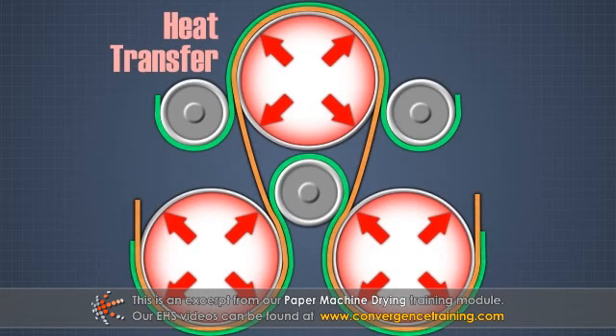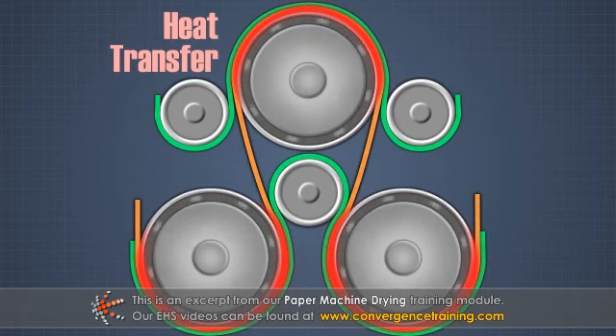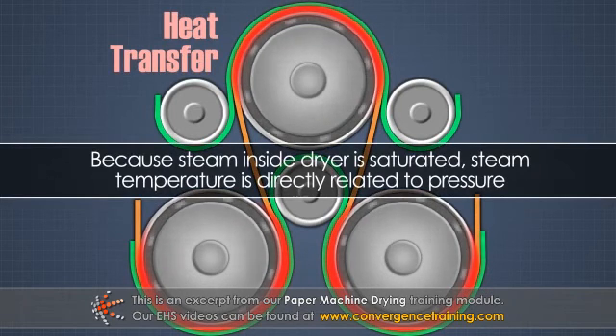The heat energy from the condensing steam is then transferred by conduction through the dryer can's cast iron shell to the sheet. Because the steam inside the dryer is saturated, the steam temperature is directly related to the steam pressure.